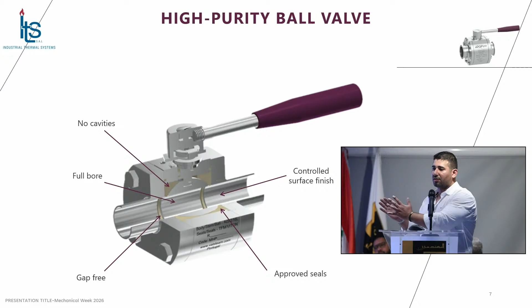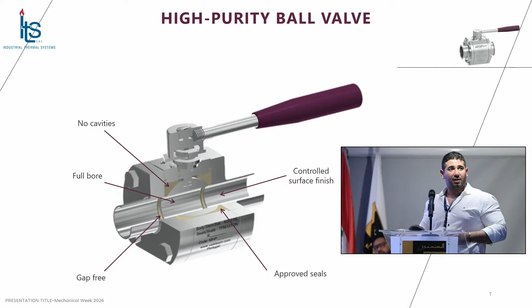One last point: we talked about no cavities, gap-free, approved seals. Ball valves are usually used for purified air or pure steam, in the utilities section, not in the production line sections. The production line sections usually use diaphragm valves, not butterfly valves like everyone uses. No matter how good the butterfly valve design is, it still has air gaps in certain spots, and stagnant points in certain spots.